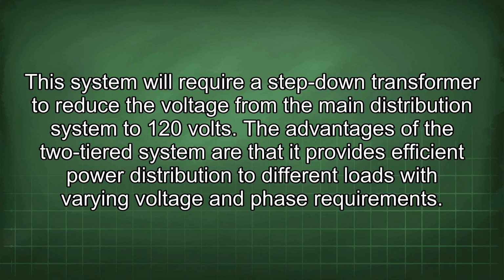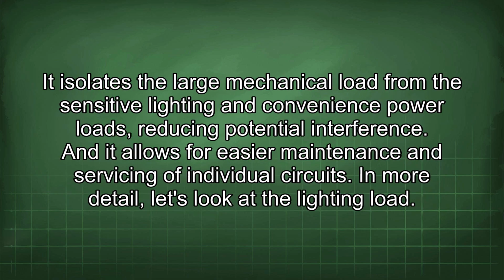The advantages of the two-tiered system are that it provides efficient power distribution to different loads with varying voltage and phase requirements. It isolates the large mechanical load from the sensitive lighting and convenience power loads, reducing potential interference. And it allows for easier maintenance and servicing of individual circuits. In more detail, let's look at the lighting load.